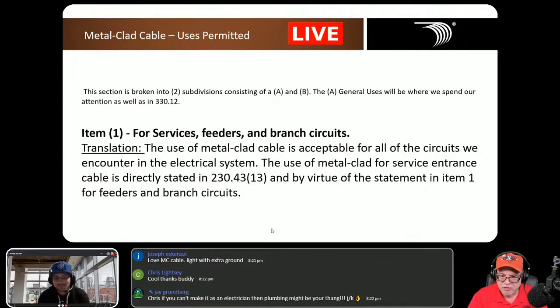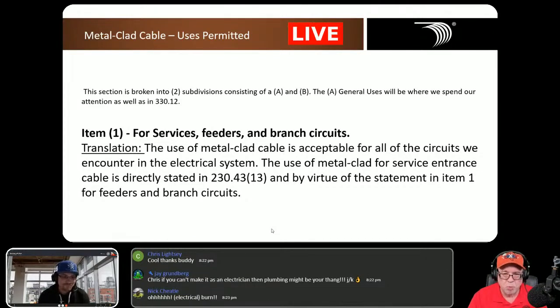I'm going to give my translation. The code language is what's in bold, and my translation is what comes below it. So item 1, for services, feeders, and branch circuits: the use of MC cable is acceptable for use in all circuits we encounter in an electrical system. The use of metal-clad for service entrance comes directly from the reference in 230.43, item 13. By virtue of the statement in item 1, I can use it for branch circuits and feeders, it says it right there. Branch circuits fall under 210, and feeders are under 215.